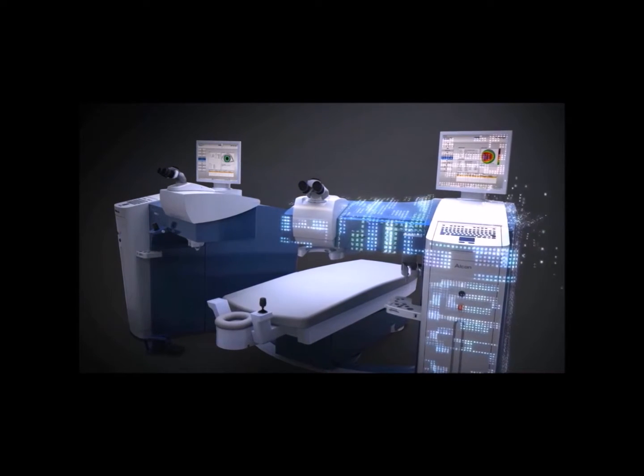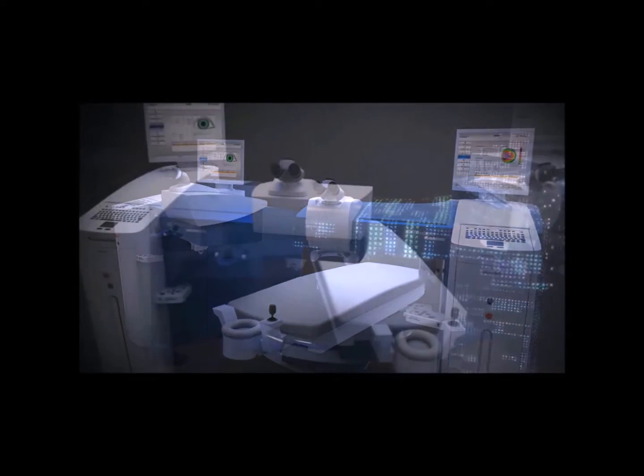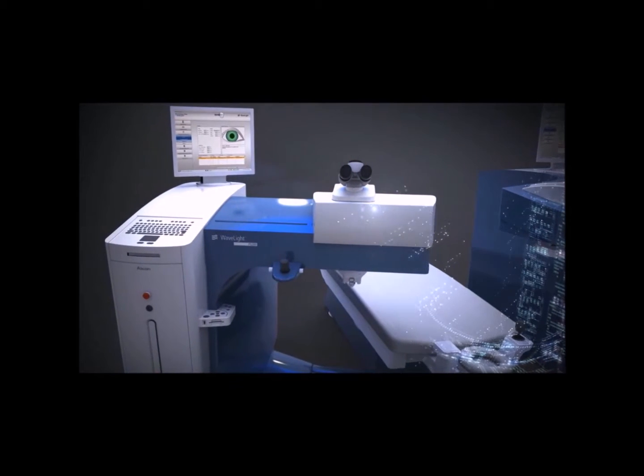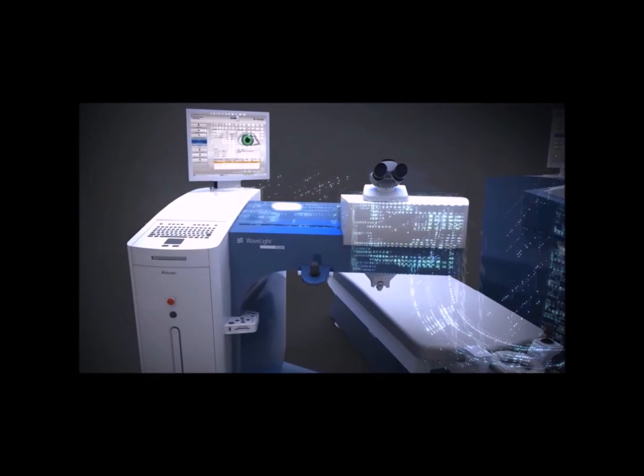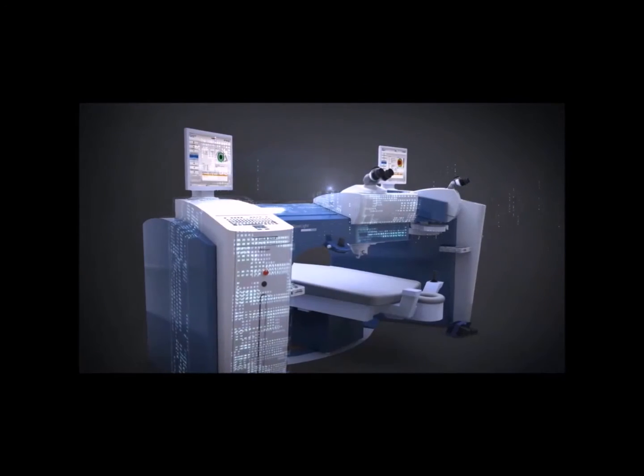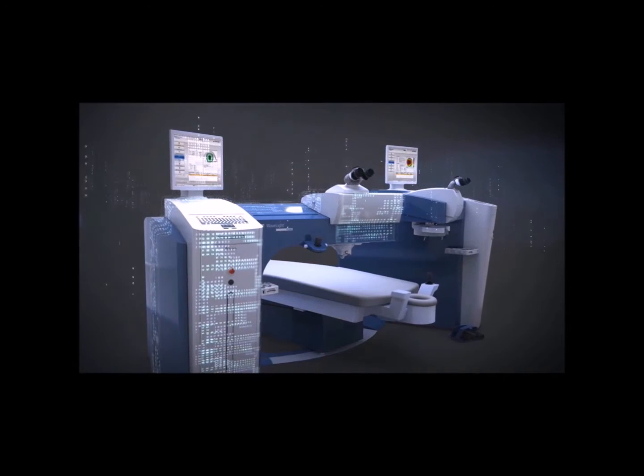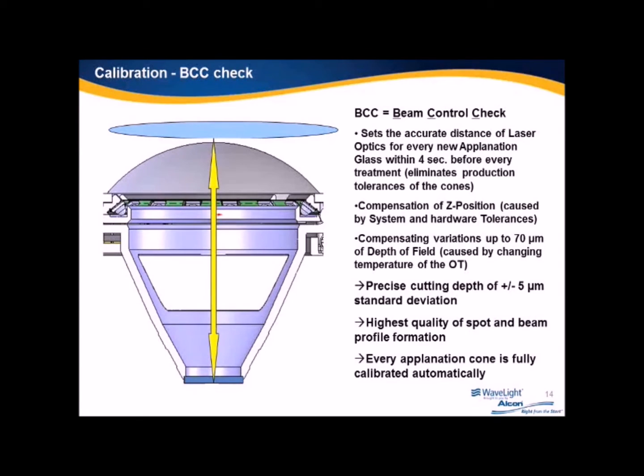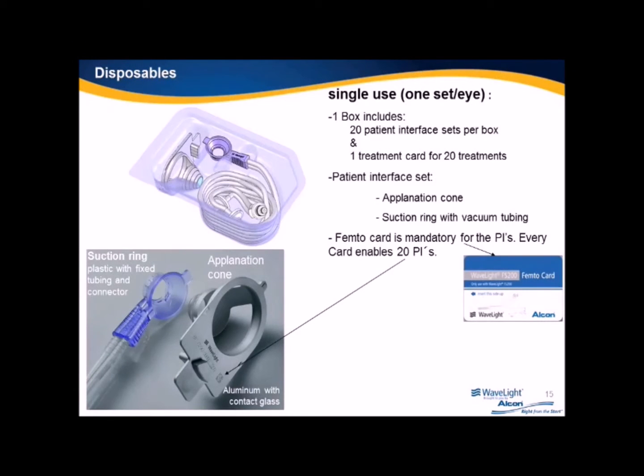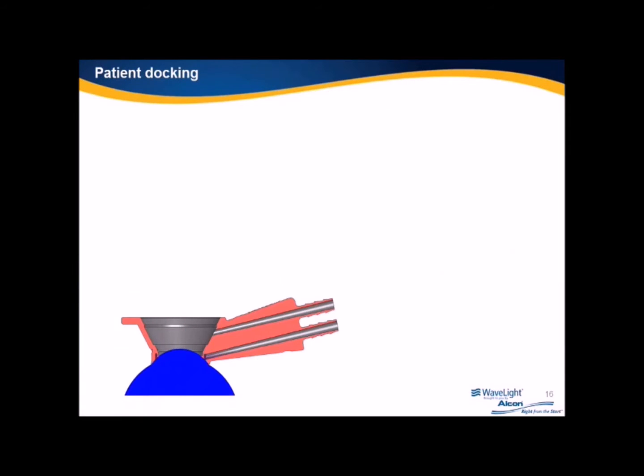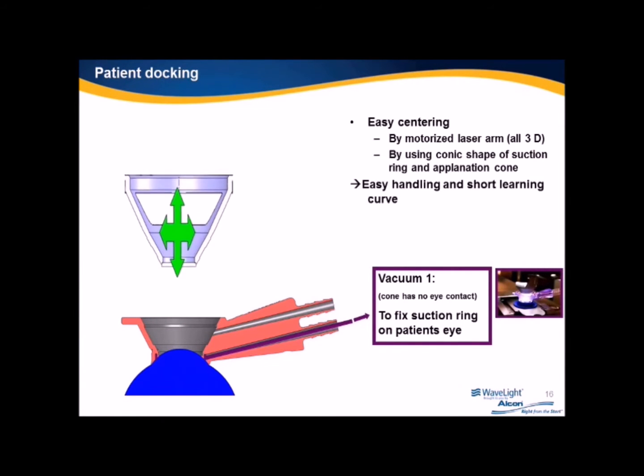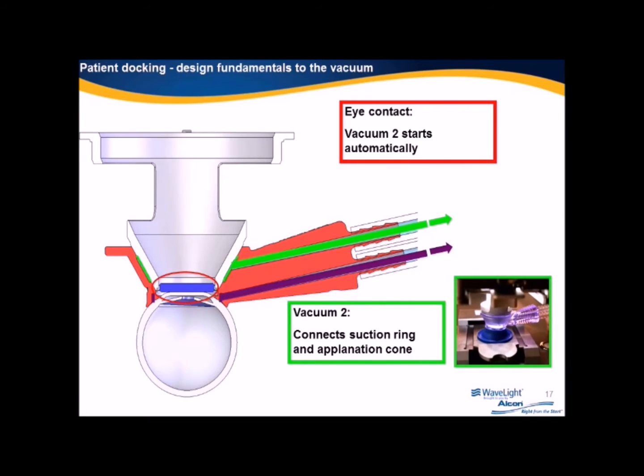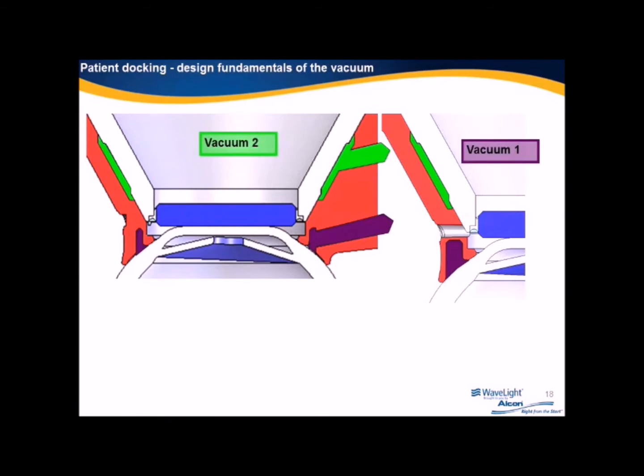Once that data is transported to the laser system, we'll make the flaps. I do sequential flaps — I'll do one eye, and if everything's perfect I'll do the other eye, then move to the other side. The newest software is reducing our suction times to a new low. The laser itself is sub nine seconds for making a flap. There are checks and balances in the system happening seamlessly behind the scenes, and you get warning devices to confirm that vacuum one and vacuum two are good.